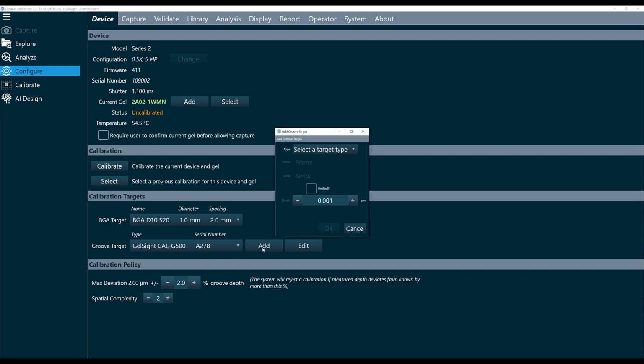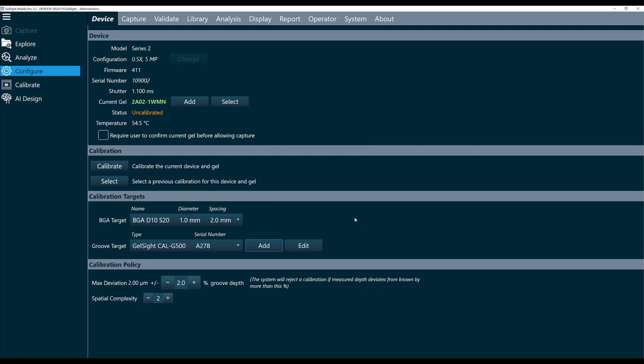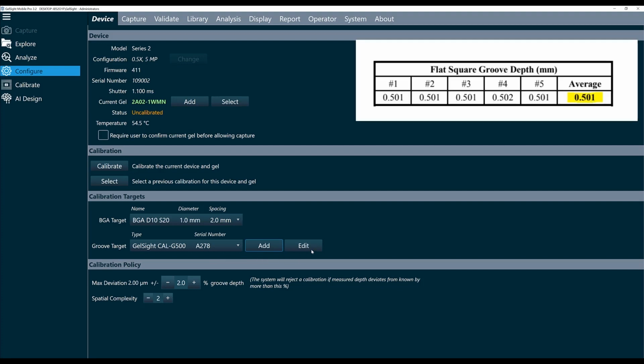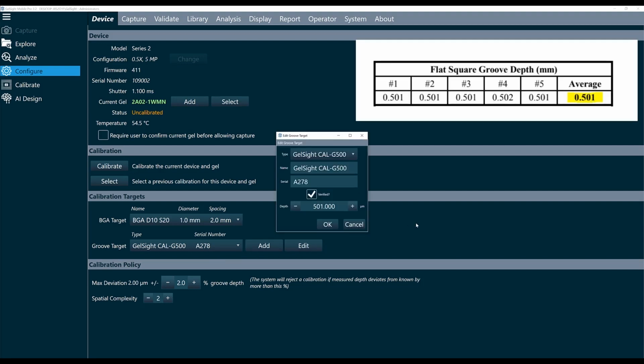If you need to add a new target because you don't see your serial number on this list, you'll click Add. You'll select your target type, G500, and type in the serial number here. And then you will enter the depth that is specified on your certificate. To verify what my already existing target has as the depth, I'm going to click Edit. I can see from this field that I have a depth of 501 micron for this A278 target, and this matches my certificate.